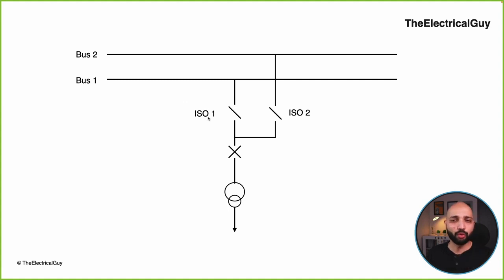Now here we have two isolators. Isolator 1 is connected to bus 1 and isolator 2 is connected to bus 2. And below it, we have different equipment that we see in the substation. Now, when the situation is normal, bus 1 is active, and in that case, isolator 1 will be closed. So you can see bus 1 is active, isolator 1 is closed, and isolator 2 is in open condition.